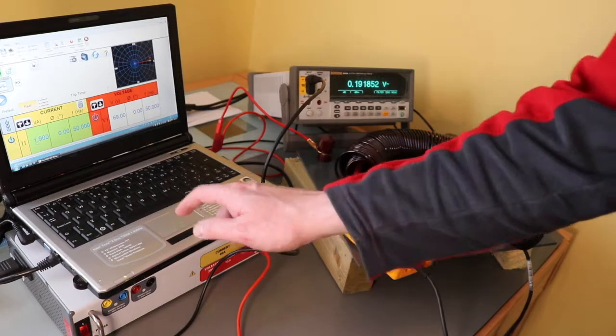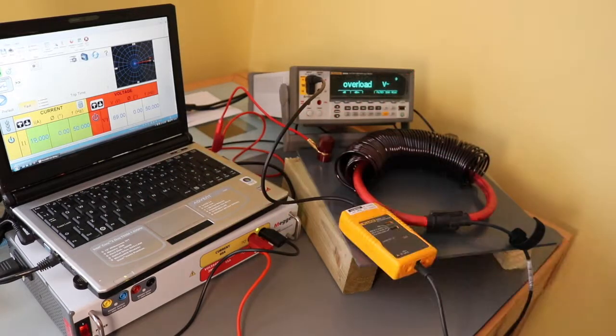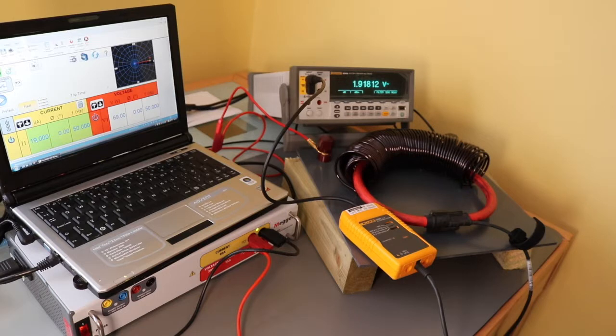If I now take this up, it should go down to 0.19 volts — reading 19 amps. And it should go back up to 1.9 volts, because that should be 1,900 amps equivalent going through the coil. So yeah, it all seems to be working fine.